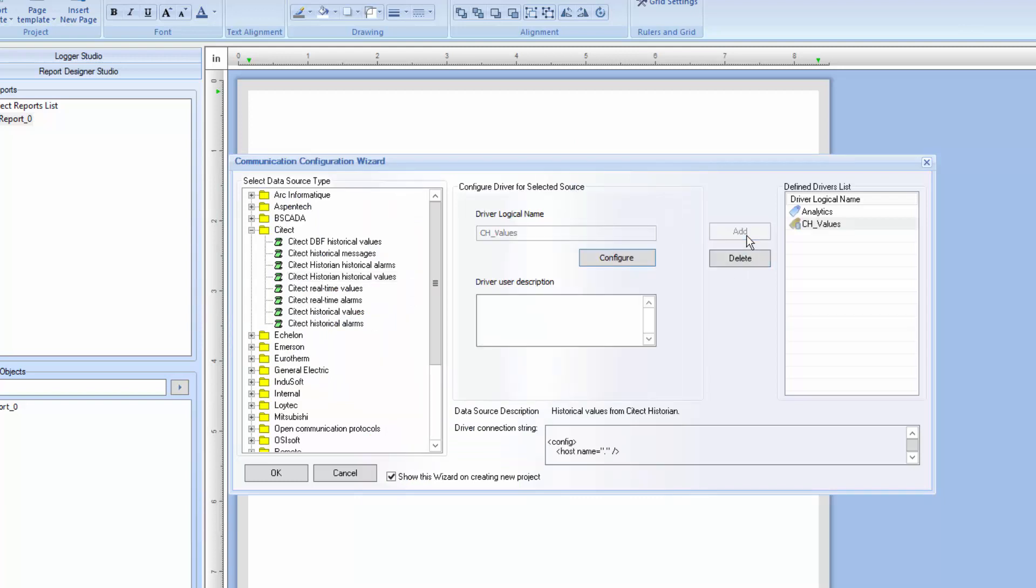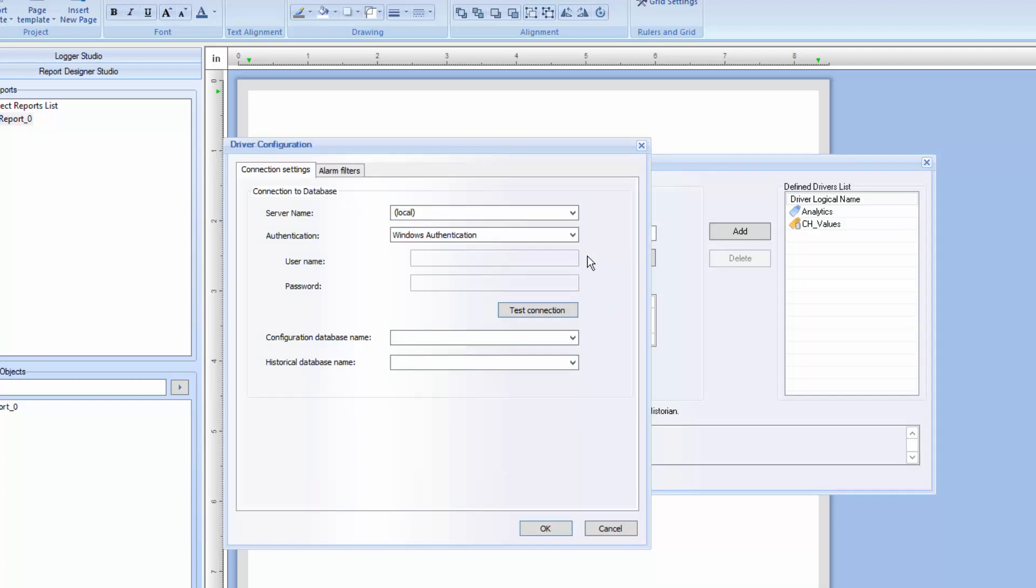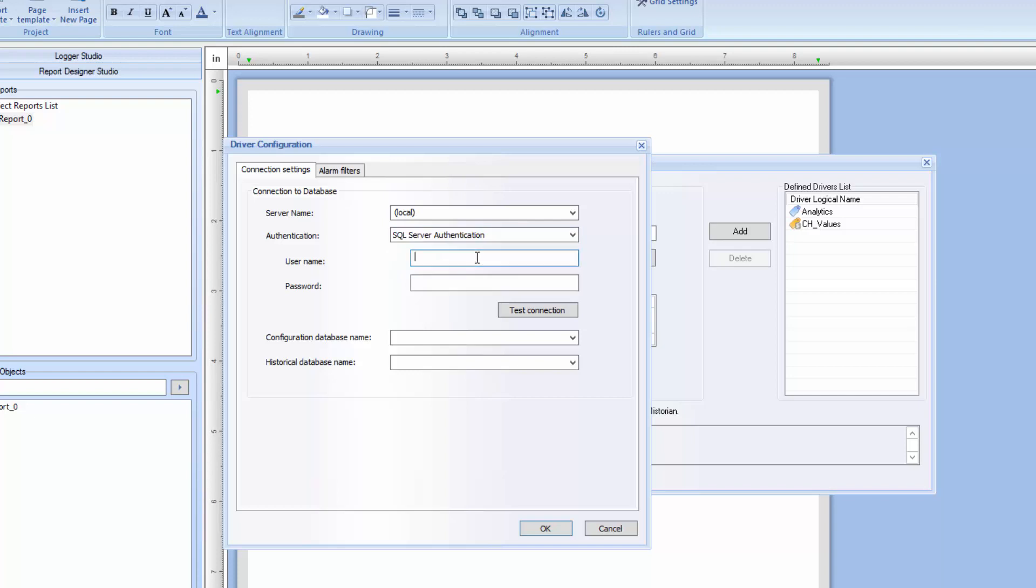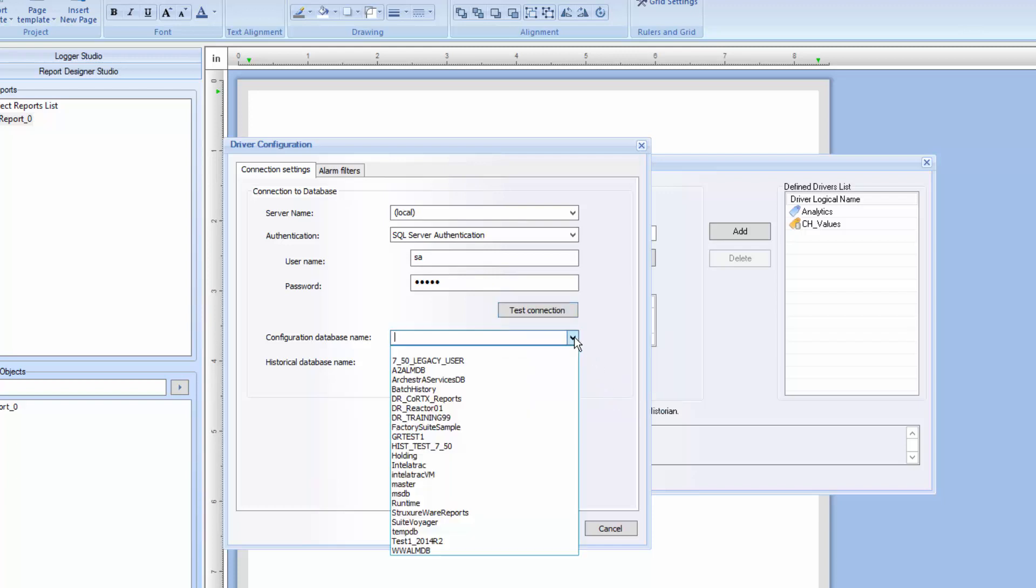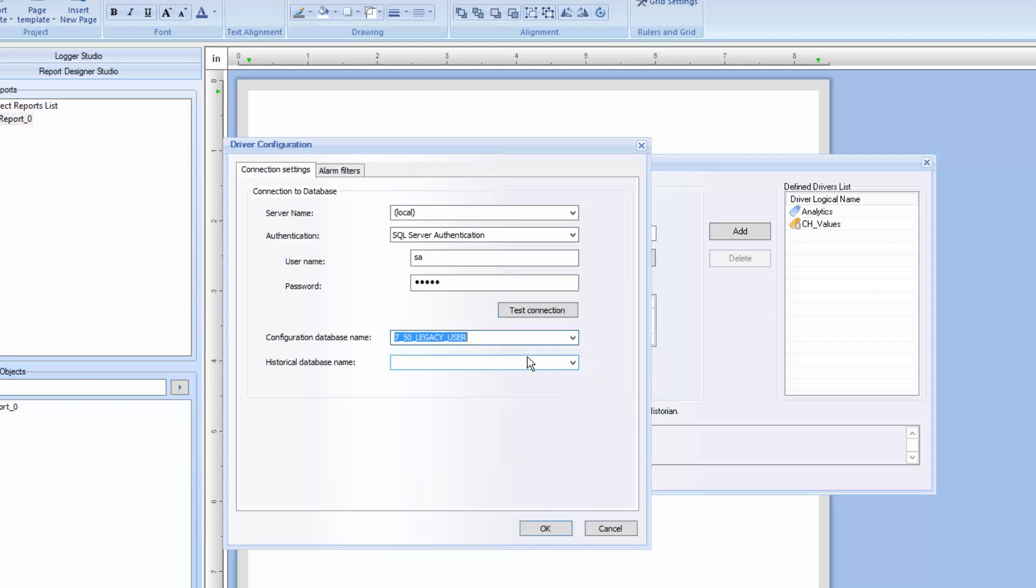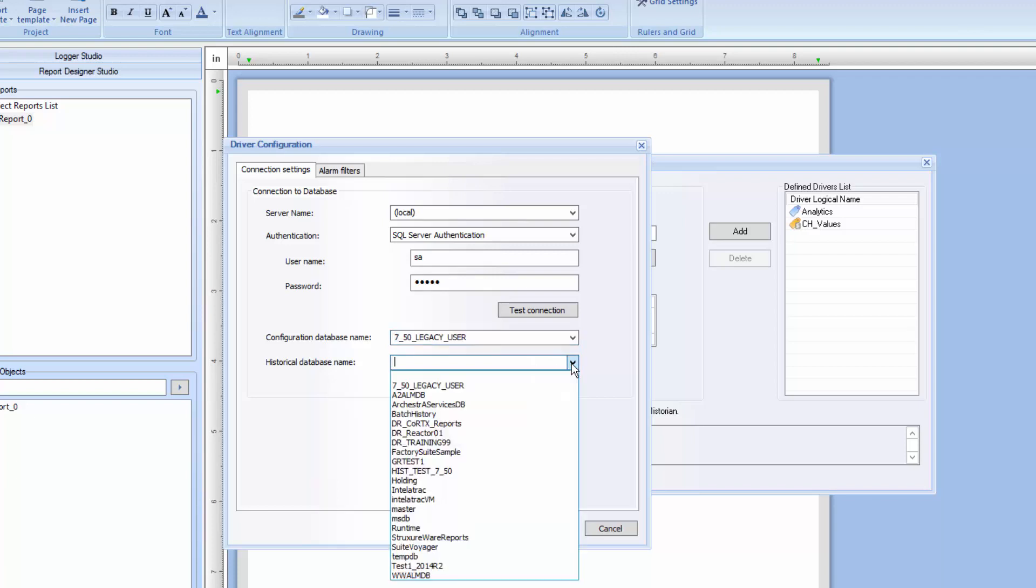Likewise, I'll configure an instance of the Citect Historian Historical Alarms driver which can access either a local or remote Citect Historian alarm database. We'll first add a logical name and then configure the driver. As in the previous example, we'll start by entering the name of the SQL Server containing the Citect Historian configuration and historical data and alarms databases. Next, we select the SQL Authentication mode. Again, I'll use SQL-based. Let's test the connection before we continue. Finally, we need to select the Historian's Configuration database and the historical database name.